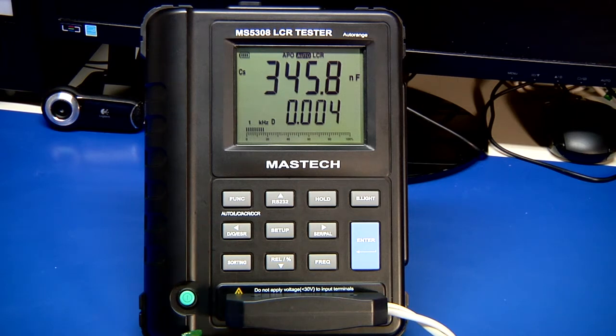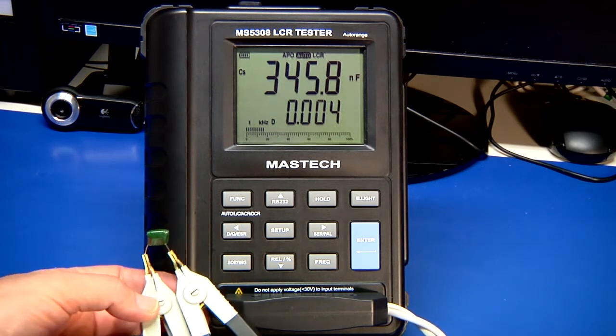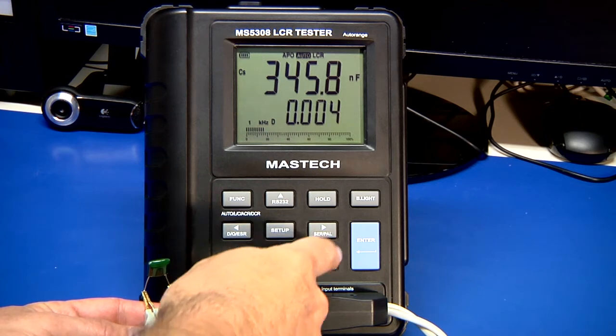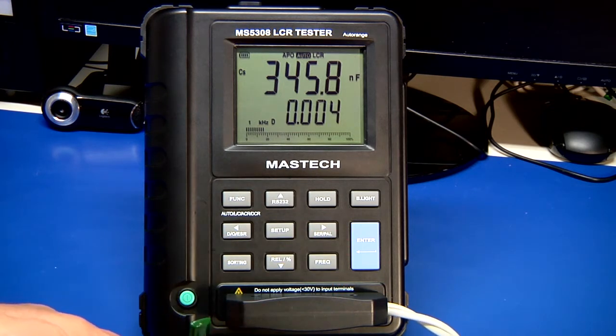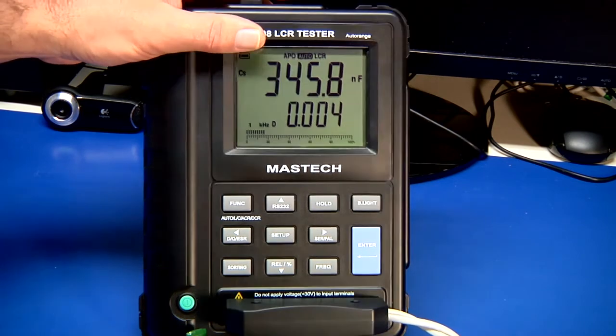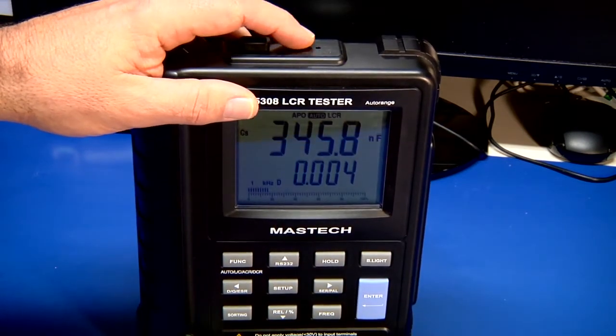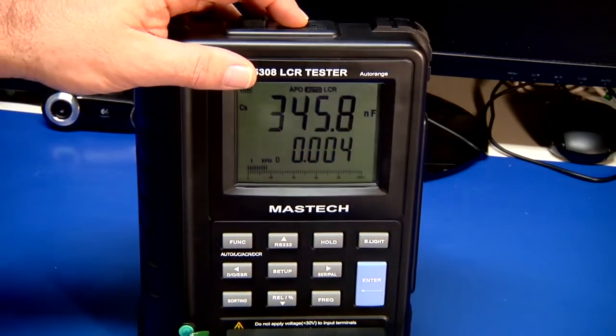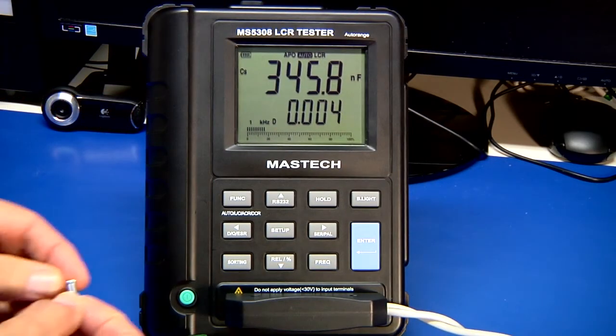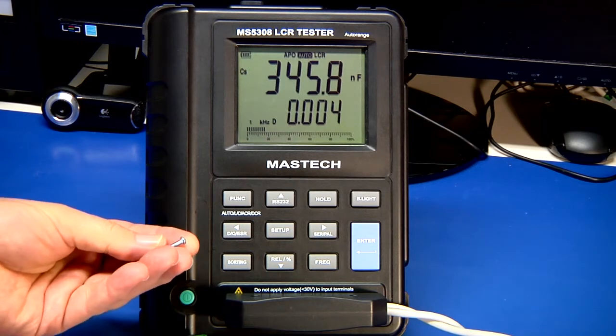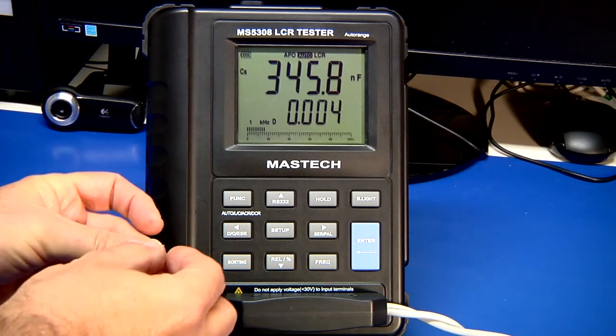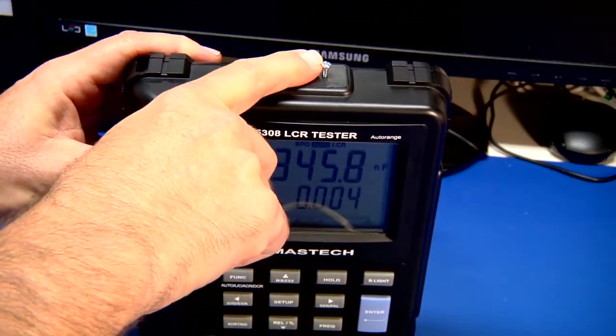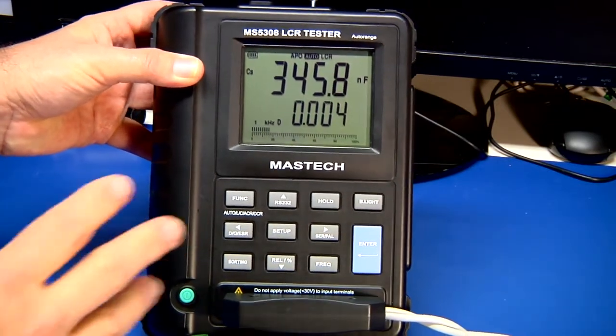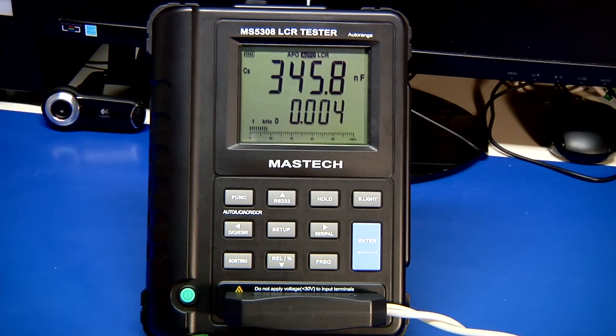Okay, I've already calibrated this unit to this particular fixture. You can have different fixtures, for example, and then you should calibrate them. As I indicated before, some units have a button on the front panel that you press for calibration. This one actually has a little recessed hole in the top right here, and when I got it, it was all scratched up, so they must have been doing a lot of calibration. I found that a 3mm by 12mm machine screw actually fits in the hole up there without bouncing around much. So you can just drop it right in there, and then you have a little place where you can press it. Again, normally I would set it up on the particular jig, and I'm not going to be doing calibrations every minute.